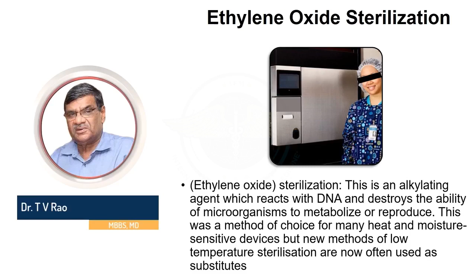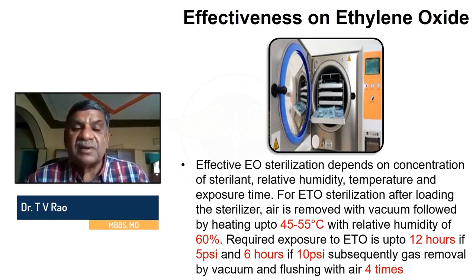Everything is locked. You cannot switch it off half-heartedly before completion. There is built-in software, and it will switch off only after the cycle is complete. Suppose you are using an incubator, you just open the door and can start working without fulfilling the regulations. Next comes plasma sterilization. Plasma is defined as a highly ionized gas composed of ions, electrons, and neutral particles. Plasmas are generated by introducing a precursor gas or vapor, hydrogen peroxide or peracetic acid, into a chamber under low vacuum conditions and then exciting the gas or vapor.